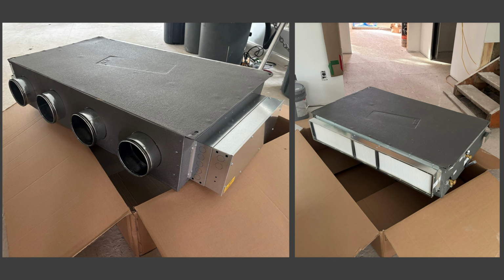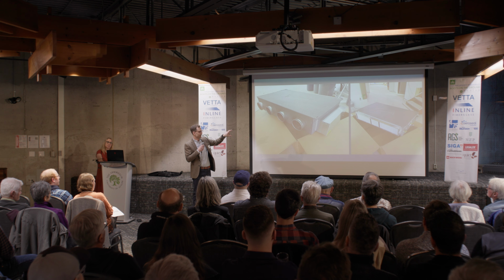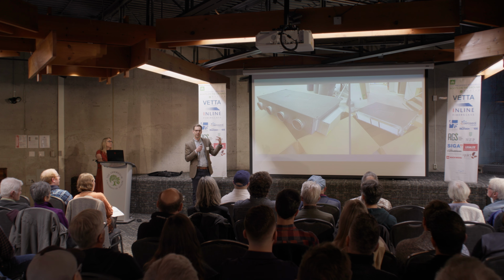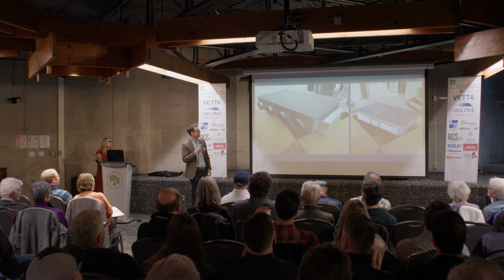What makes these interesting is that most fan coils just have a coil and a single fan, and if you wanted to subdivide that air you could put in a motorized damper system, but that adds additional complexity on site. What's interesting is inside this box there's a single coil, but there are 4 fans. That duct gets piped out to a bedroom, say, and there's a thermostat in that bedroom, and that thermostat tells that fan to run or stop if the setpoint's satisfied.